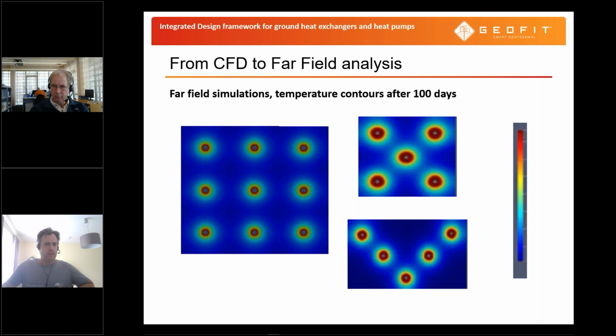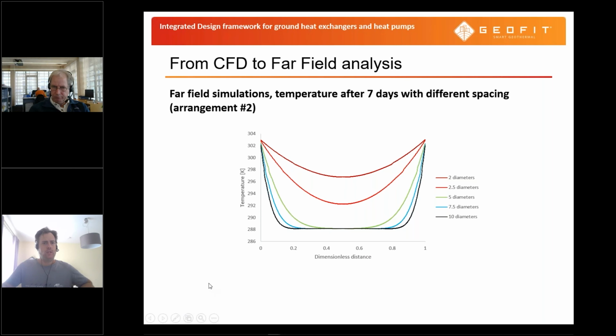So this is, let's say, the qualitative analysis. When we take a closer look at arrangement 2, which is shown here after 7 days with different spacing, from a spacing of 2 diameters of one earth basket up to 10 diameters, you see that the temperature in between 2 baskets is not, or far less, affected when you put the baskets at a bigger distance rather than having them close together. When you think about it, it's obvious that you get such results.